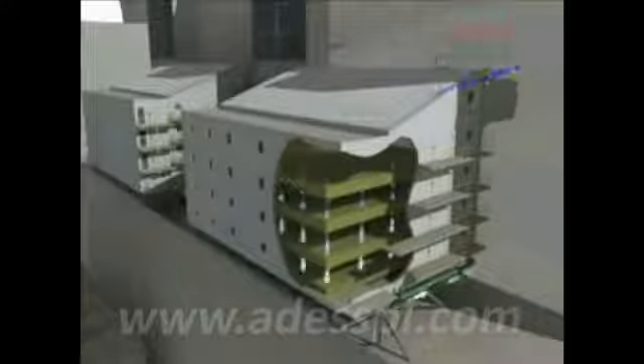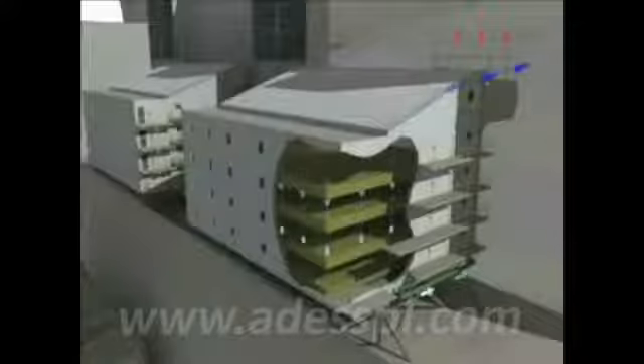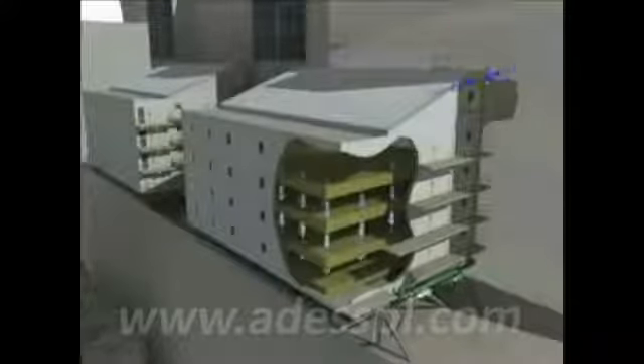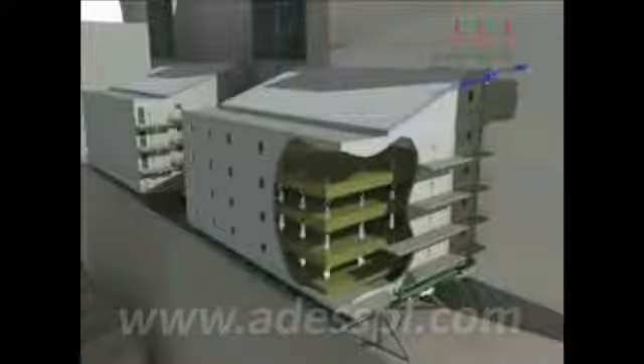SCR systems work much like a catalytic converter on a car. Flue gas containing nitrogen oxide emissions from the combustion process is mixed with ammonia. The mixed gases travel through a series of catalytic layers, which causes the nitrogen oxides to react with the ammonia. The reaction converts the nitrogen oxides to water vapor and pure nitrogen, a benign chemical that makes up 80% of the air we breathe. Both elements are returned to the environment through the station's stacks.